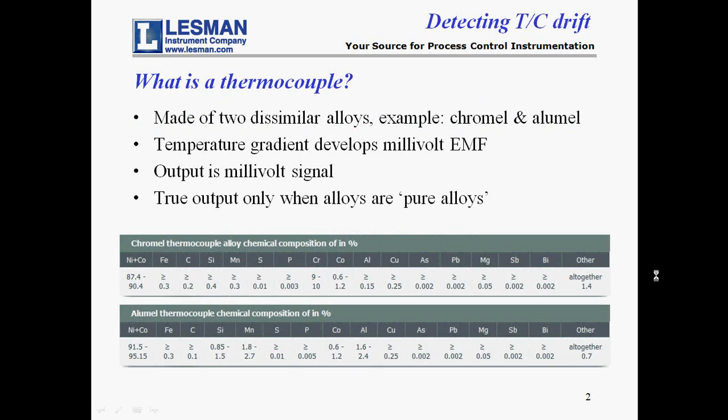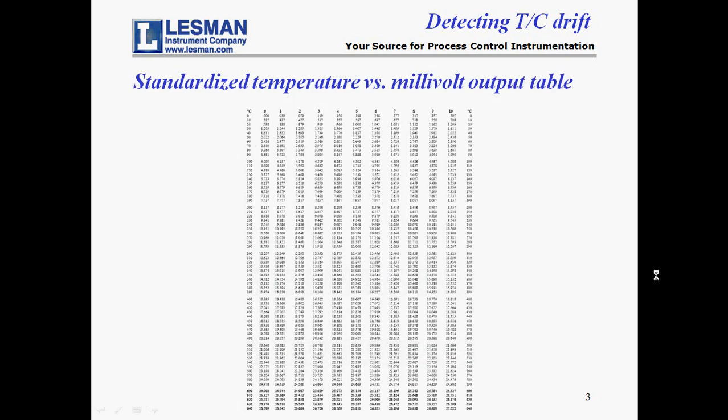A thermocouple is made of two wires of different alloys, commonly called the dissimilar metals. For instance, a K-type thermocouple is made from chromel and alumel alloys. The alloys produce an electrical millivolt signal that varies with temperature. The pure alloys that form the thermocouple's junction have a low electrical resistance and the thermocouple's output is true as long as the alloys remain pure. The temperature versus millivolt values generated by a thermocouple are published in standardized reference tables. Electronic instruments use these tables to produce temperature measurement values.